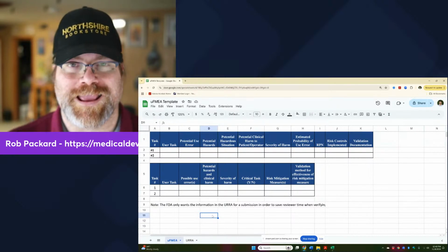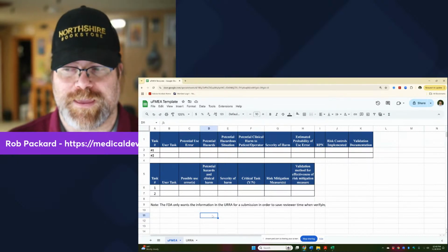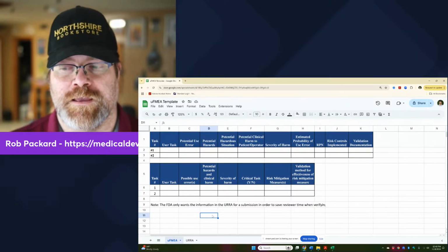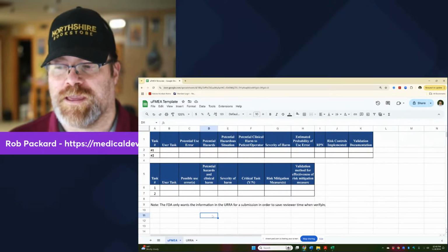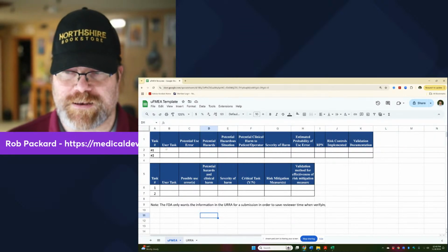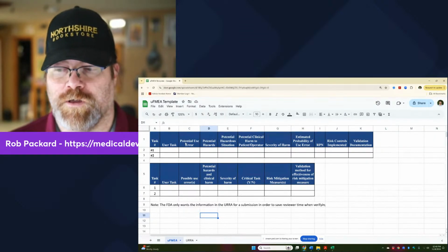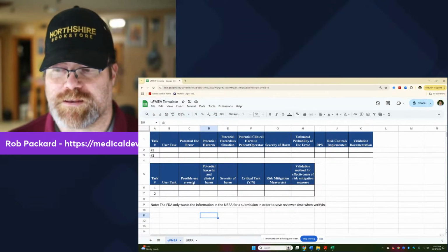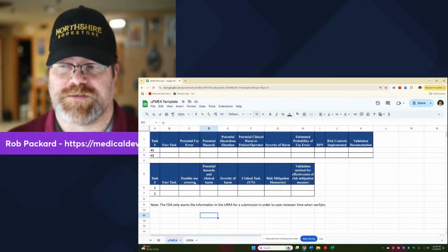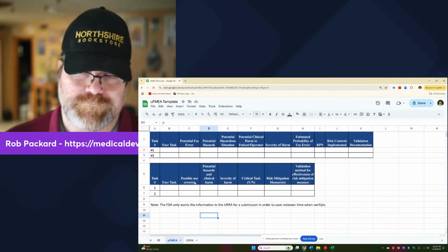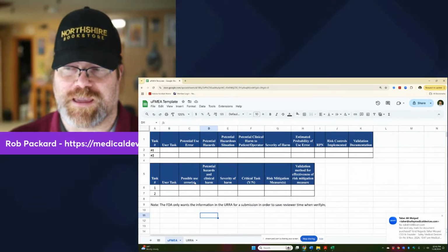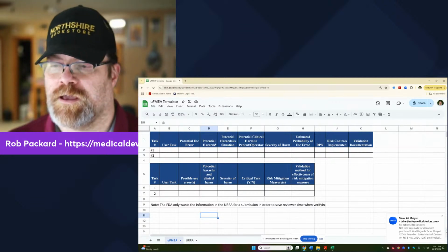Well, this doesn't line up exactly with the uFMEA. So if you've done a uFMEA like I've shown on here, and you see what the FDA wants, here's what you do. The first column is identical. The second column is identical. The third column is almost identical. One says errors with S in parentheses. The other one says error. That's just a heading, so the content is the same. The heading is slightly different.